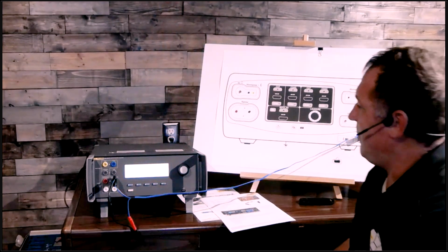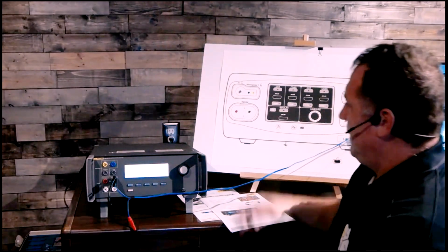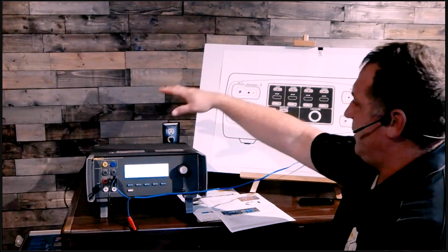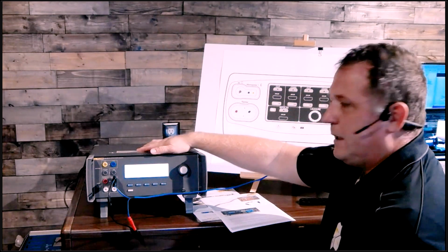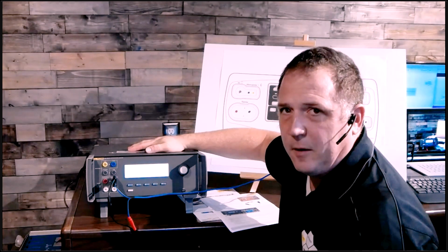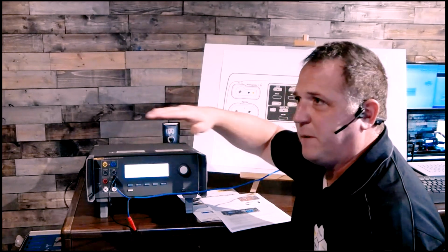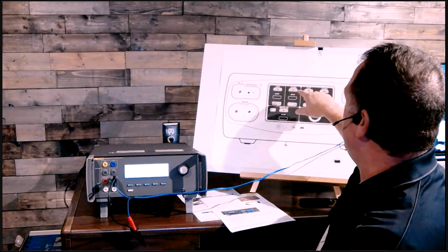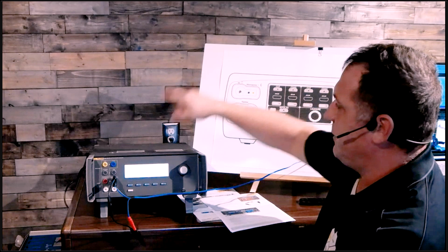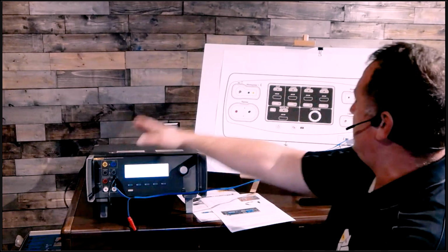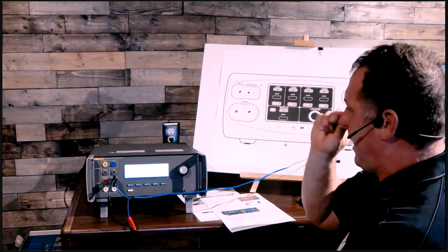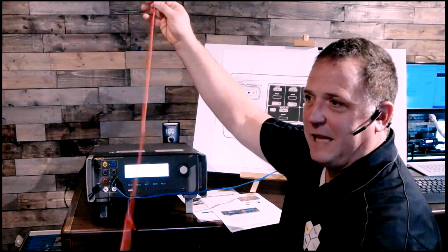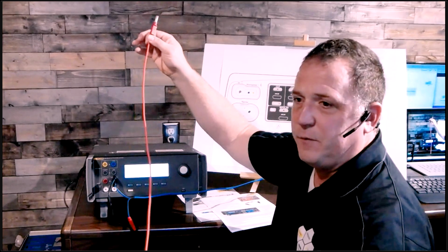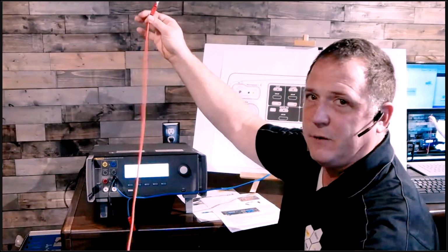The next thing I should probably mention is as you're doing your testing, you notice that my ESU is not sitting on top of my analyzer. A lot of the frequencies we operate now are just below RF energy, so you can actually transmit radio frequency from this to your ESU and skew your answers. So you want to make sure these two devices are not stacked on top of each other and that you're not adding length to these cables, because if you do, you just turn this thing into a radio antenna and you can transmit your signal out.